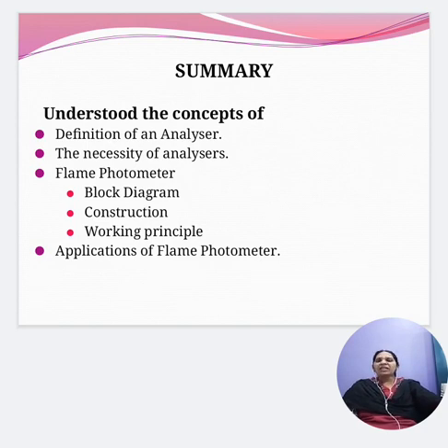So photoelectric flame photometer is an instrument which is used in inorganic chemical analysis to determine the concentration of certain metal ions like sodium, potassium, calcium and lithium. So flame photometry is based on measurement of intensity of light emitted when a metal is introduced into the flame.